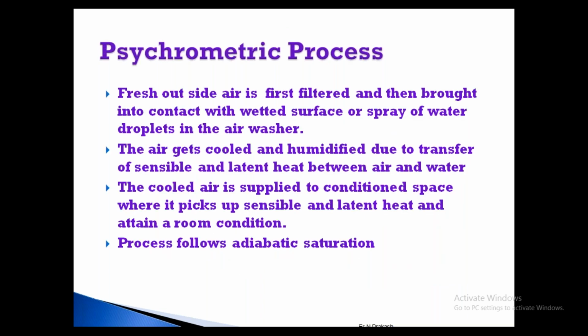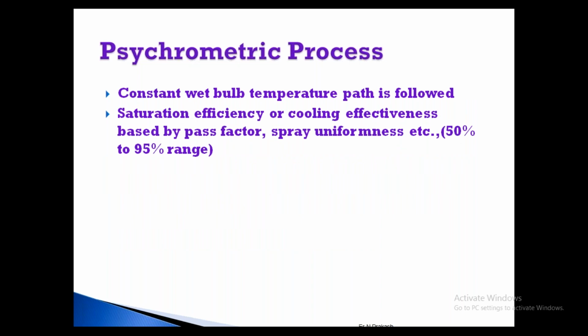So you need to know how it functions. Basically, fresh air is taken first and filtered, then brought into contact with the wetted surface with the spray of water droplets, and then it gets cooled and humidified due to transfer of sensible and latent heat between air and water. The cooled air is supplied to the conditioned space. It picks up the heat there. Already there will be heat. It picks up the heat, and you will attain a particular temperature and RH. This process totally follows adiabatic saturation, so there is no change in the wet bulb temperature. It follows the constant wet bulb path. So saturation efficiency can reach 95%, even more. But again, there is a cost involved to reach the maximum efficiency.